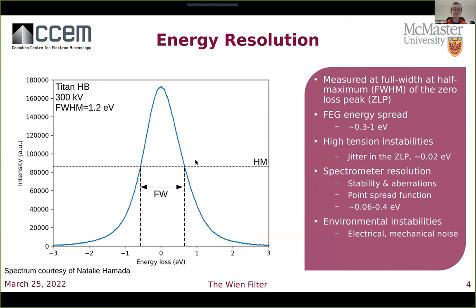This energy resolution is dominated by the energy spread of electrons as emitted from the FEG itself, and can be made worse by instabilities in the high tension, instabilities and aberrations in the spectrometer, the point spread function of the camera used on the spectrometer, or electromagnetic or mechanical noise from the environment. Using a monochromator can help us reduce at least the energy spread from the FEG in order to resolve finer features in our spectrum.